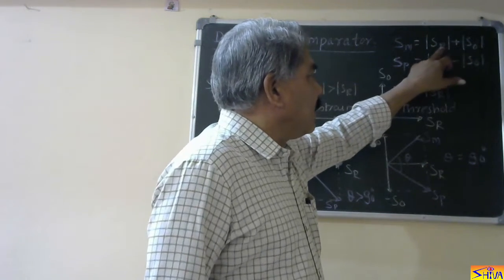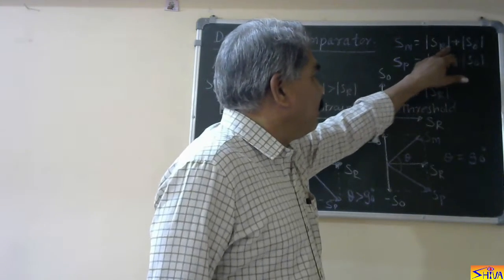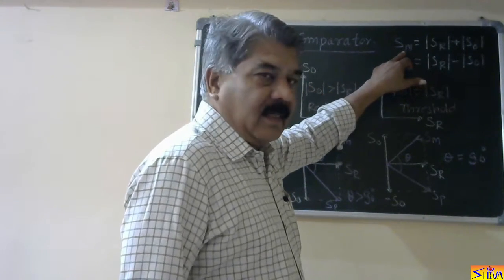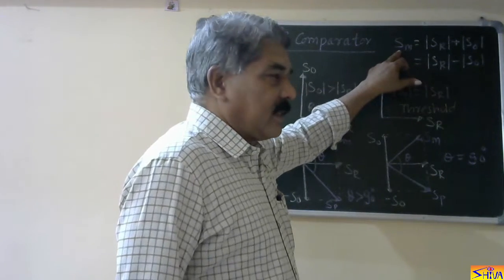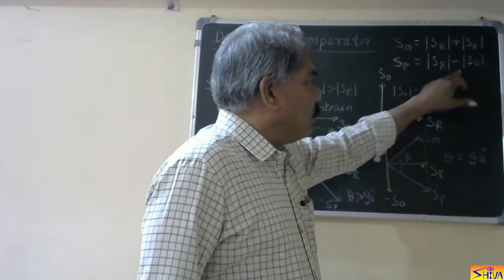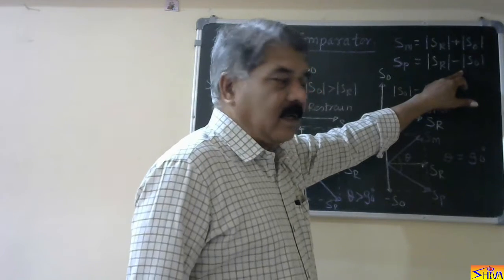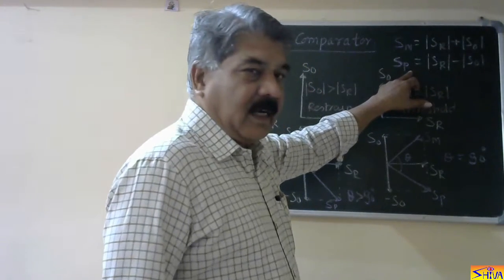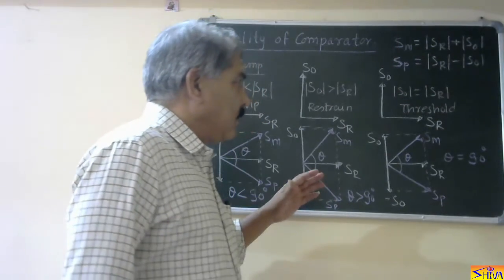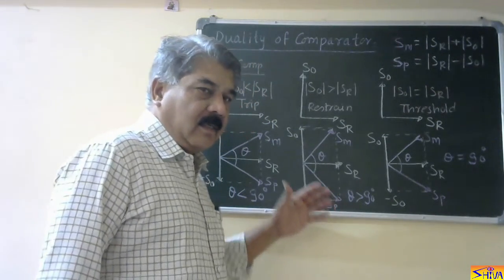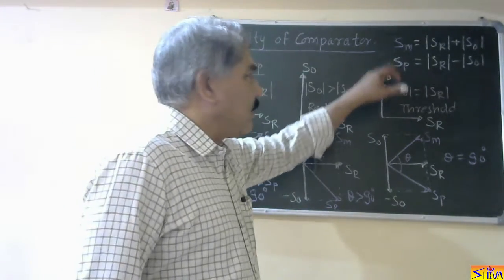These are the original inputs of the amplitude comparator: SO and SR. We are taking the sum, SO plus SR, as SM — that is the measuring or operating quantity for the phase comparator. SR minus SO, the difference, is taken as SP — that is the polarizing or reference quantity. Now let us see how phase comparison can be obtained by these converted quantities.